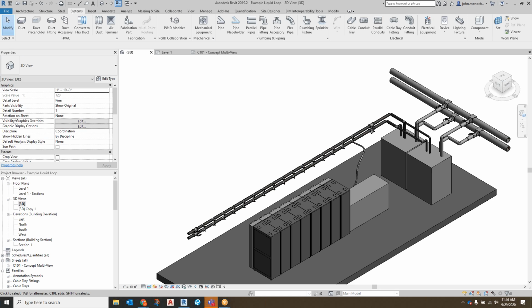Well, yeah, there are. ASME has guidelines like that, just for the design of piping distribution. The power piping codes have got exactly that, to prevent erosion in the walls of the piping from moving too quickly because of the turbulence in the elbows and other fittings. But you've got to be moving pretty fast to reach that kind of issue.